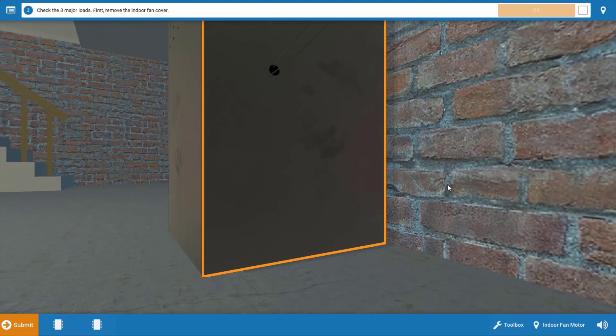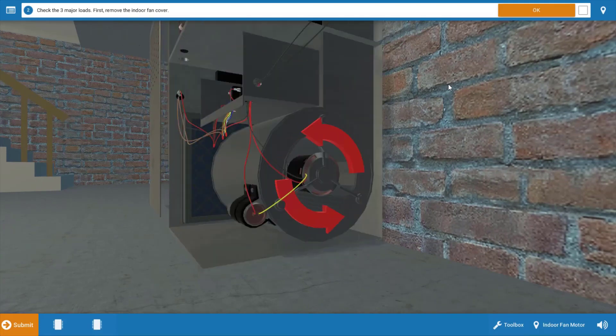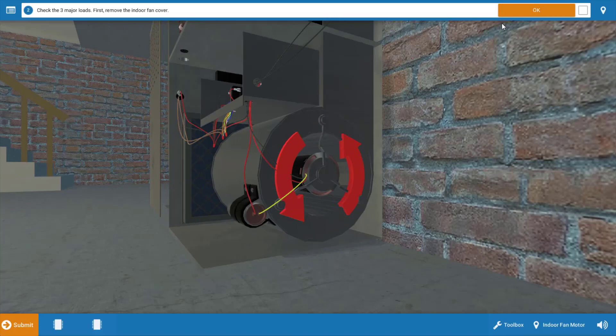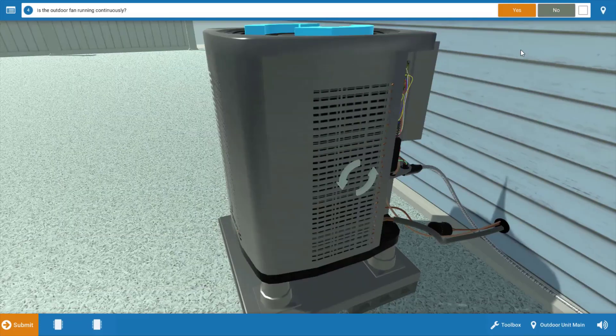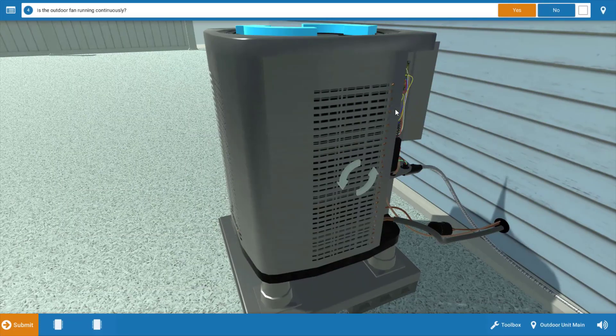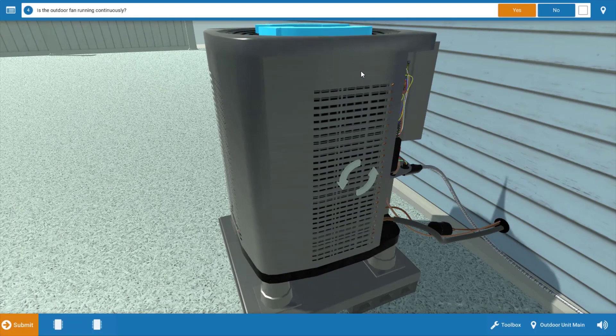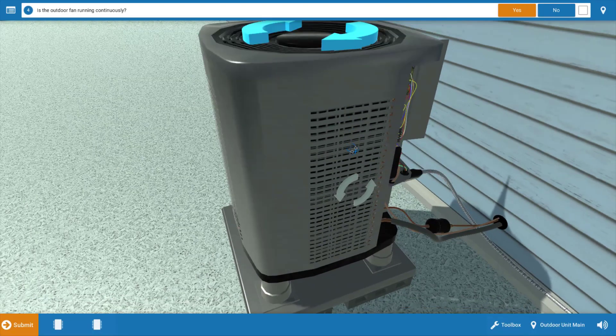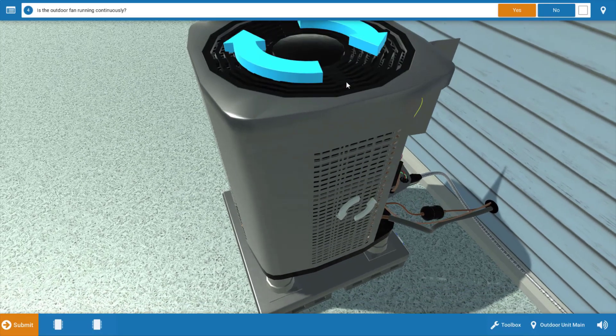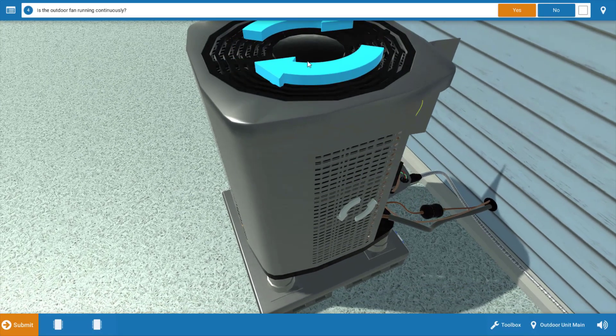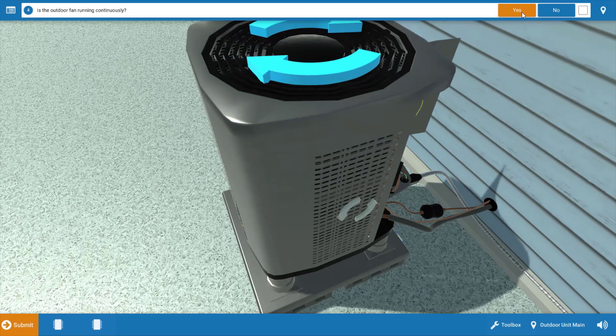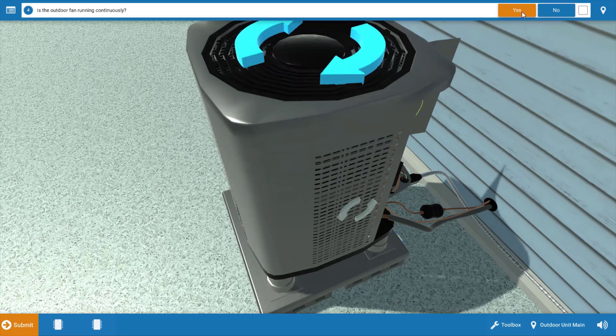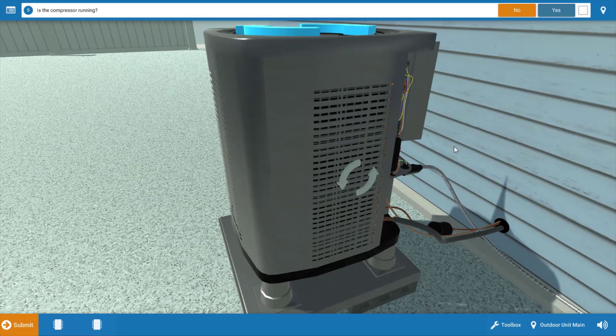Next we're going to assess which loads are operational. We're going to start at the indoor unit, and we can see that the indoor fan is in fact running, so we're going to click yes. Now, on our outdoor unit, is the outdoor fan operational or running? Well, it is. We can see that from the spinning blue arrows that the outdoor fan is running, so we're going to click yes.